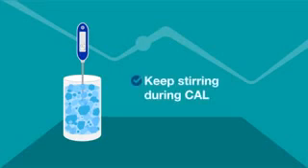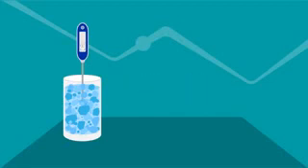The thermometer is now in auto calibration mode and will take temperature readings until a stable set of three readings has been recorded. It will lock on to the three readings and the display will flash three times with the letter C in front of the numbers.